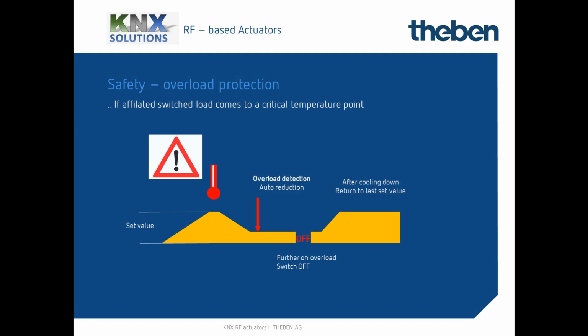What's essentially important, a feature I want to highlight for all of our flush mounted actuators, is overload protection. This means, for instance with a dimmer, if the inside discovers the temperature is rising due to overloading, the electronic inside starts to reduce the load, driving it down until switching off. After cooling down and recovering, the actuator tries again on its own to restart and return to its former value. This is an important protection against this calorific potential.